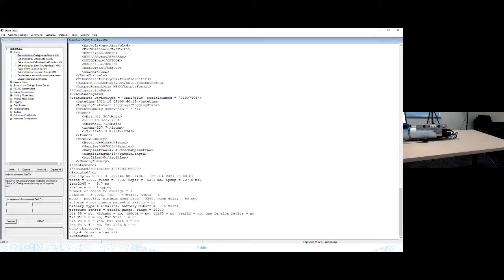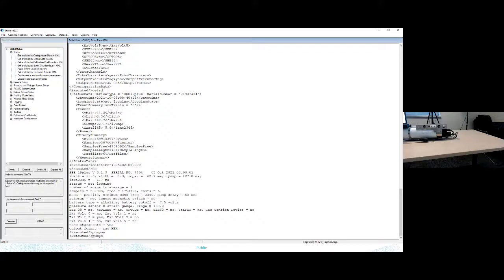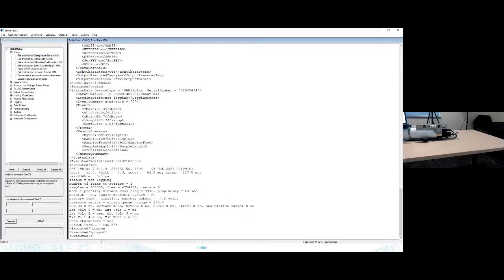You might be hearing this pretty awful sound the CTD is making - that's actually the pump running. You can send the command pump on to your instrument, and then pump off to turn it off. Word of warning: these pumps are not meant to be run dry. If you're testing it for more than a couple of seconds, I'd recommend taking some deionized water and squirting it into the pump head so it's lubricated by water. It won't be as loud, but it might splash water everywhere.